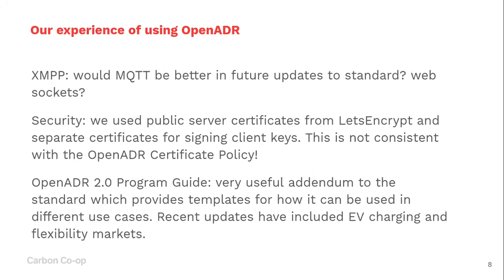Just to reflect on this initial period of development and our experience of using OpenADR, it's showing its age a little bit in terms of security. I think it relies quite heavily on the use of TLS public key infrastructure, whereas these days it's much more common for web services to obtain SSL certificates for free. In our implementation, we've used the common public key infrastructure of Let's Encrypt for the server certificates, and then we only sign the client certificates with our own keys. But it's worth saying that this isn't consistent with OpenADR certificate policy, even if it represents better practice.